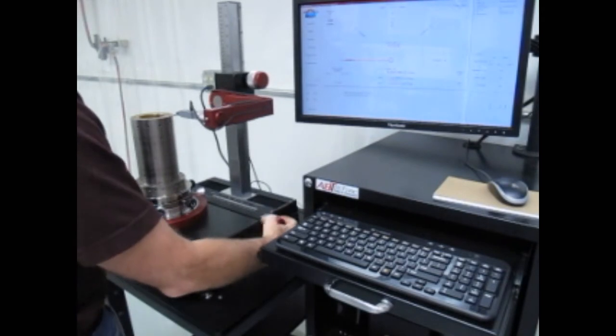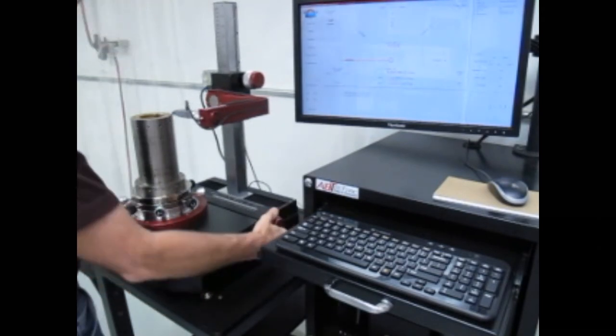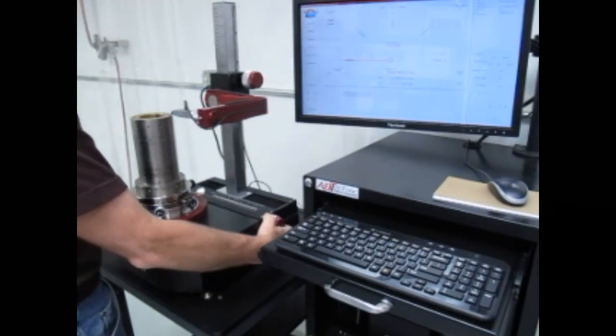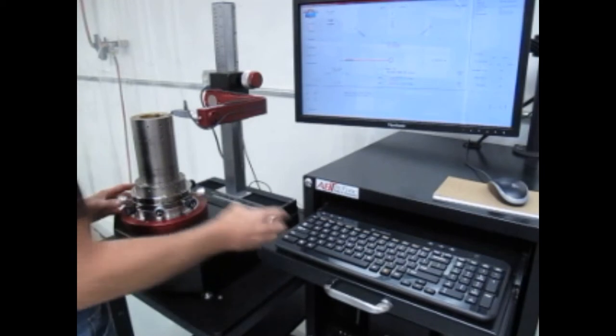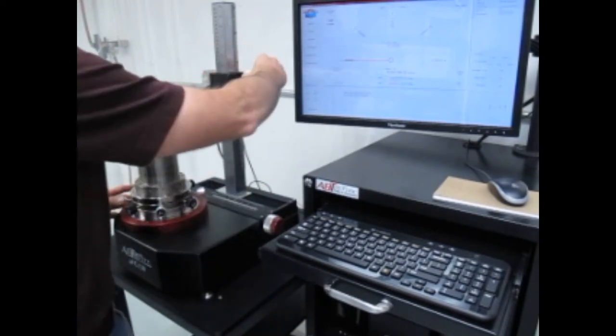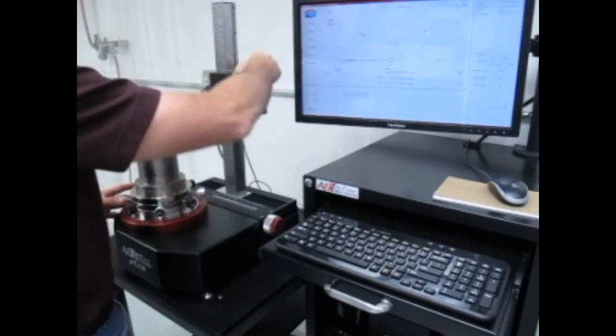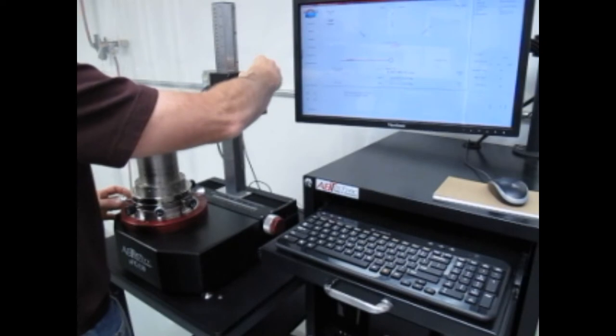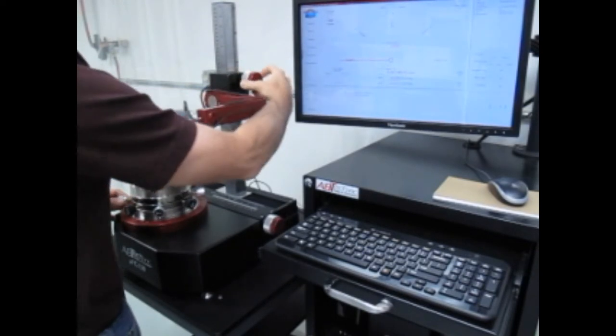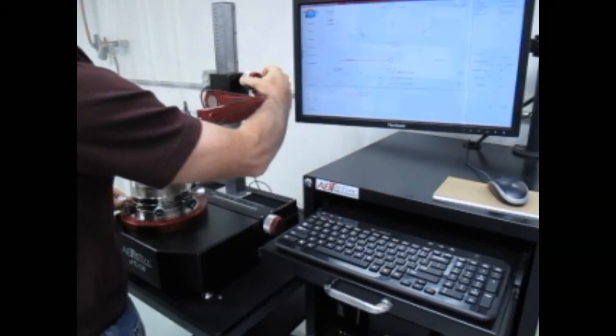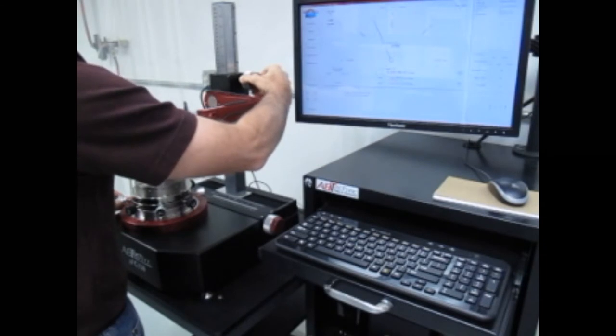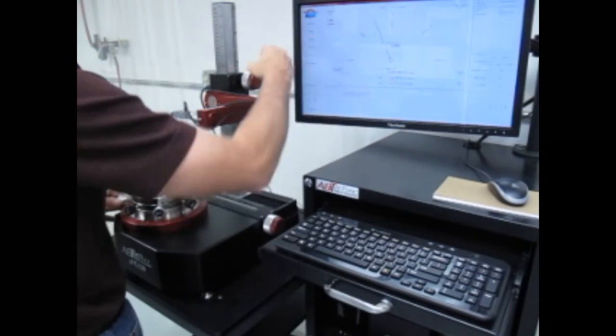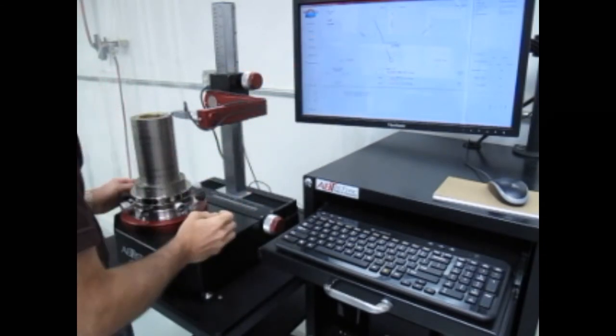And I'm going to come in to a surface and then using my setup screen here, and then the coarser scale, which is the full travel of the probe, I'm going to come into contact with it. You can see it turned from red to black on the VRO and the needle comes up.